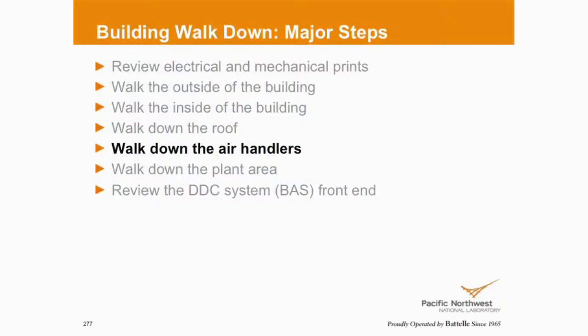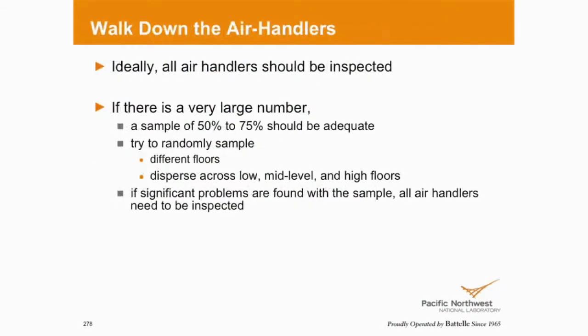Then we're going to look at air handlers. How many do I have? I know the building we're going to look at tomorrow has almost 20, I believe, air handlers, so we're not going to look at all 20, believe me. If I'm walking them down, I want to get a sample, maybe up to 50%, so that might mean looking at 10 of them. I don't know that we'll look at all 10 tomorrow. But I want to get a random sampling. If I find a problem, I want to go to the next one and see if it's consistent. Is it because of the vendor? Is it how I'm doing maintenance or not doing maintenance?